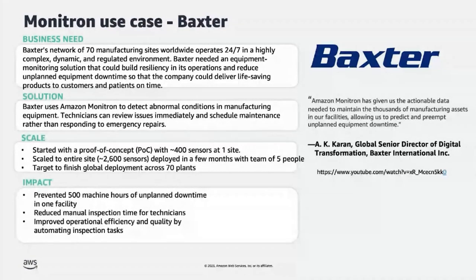They started their journey with Monitron at one site — a cooling tower that provided chilled water for two production areas to maintain room temperature. They started with around 400 sensors installed at this site. They ran the POC for a couple of months, but within the first month they started to see value. Monitron detected an anomaly on a gearbox that was close to failure, which helped Baxter save approximately 396 hours of machine downtime. Over time, they have scaled to the entire site with around 2,600 sensors, deployed in a few months with a team of five people. They are scaling to other global manufacturing sites with a target to finish global deployments across 70 plants.